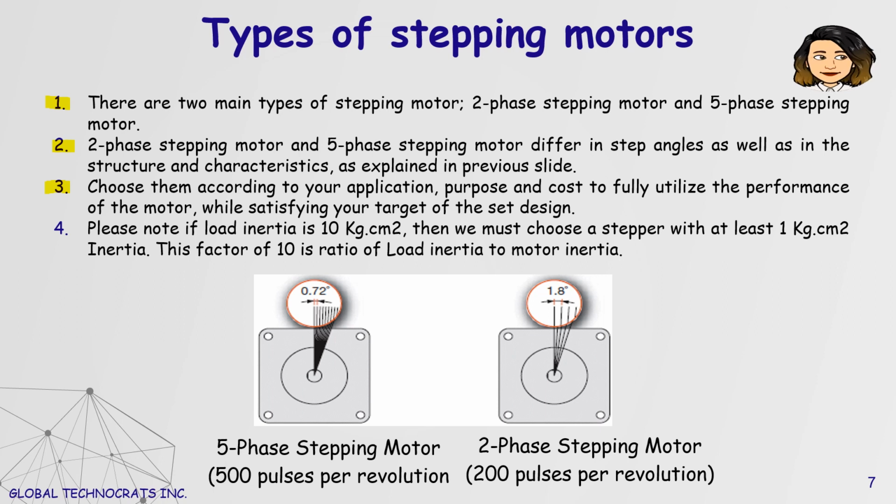Please note, if load inertia is 10 kg centimeter square, then we must choose a stepper with at least 1 kg centimeter square inertia. This factor of 10 is the ratio of load inertia to motor inertia.